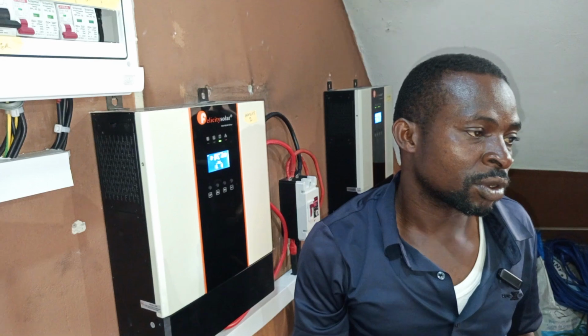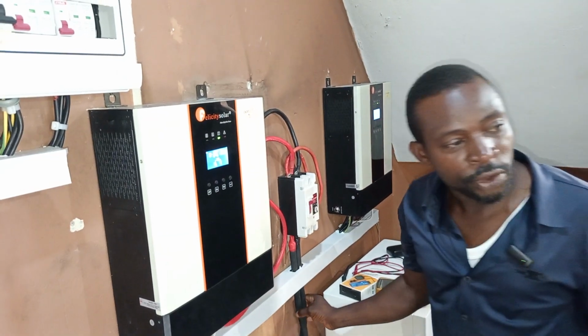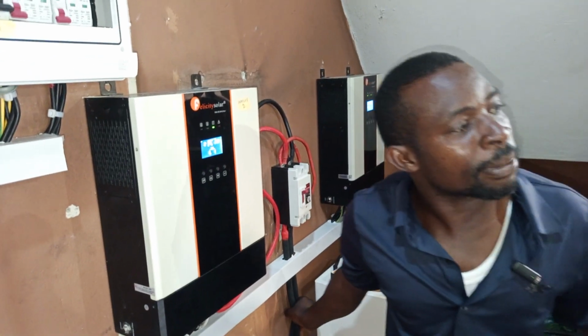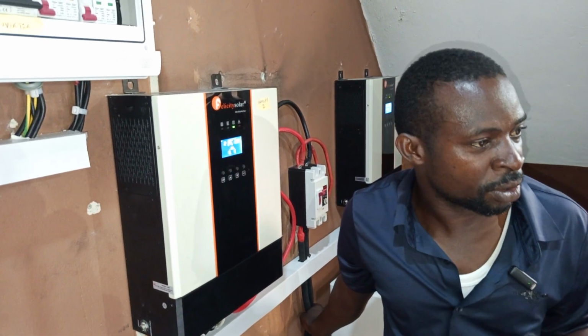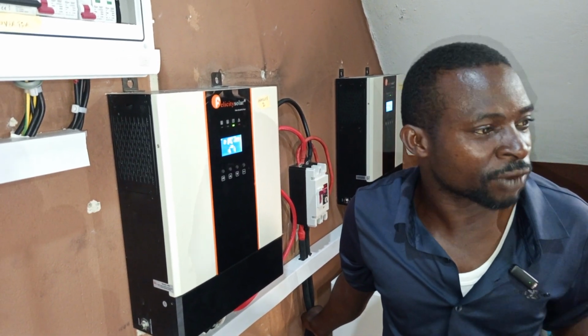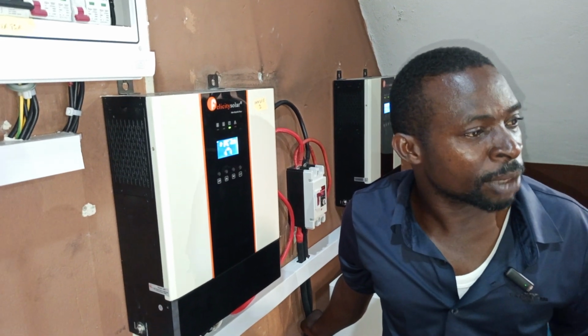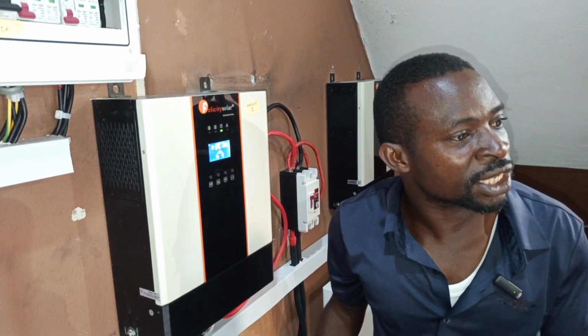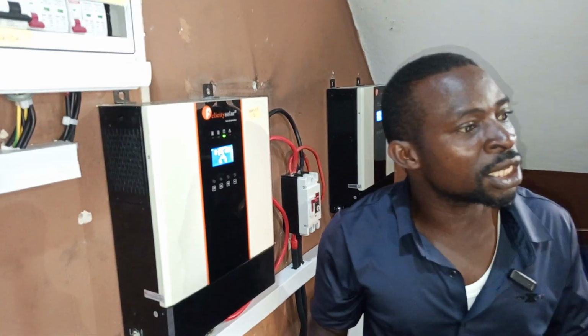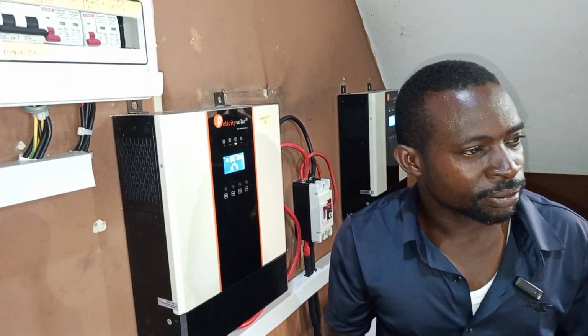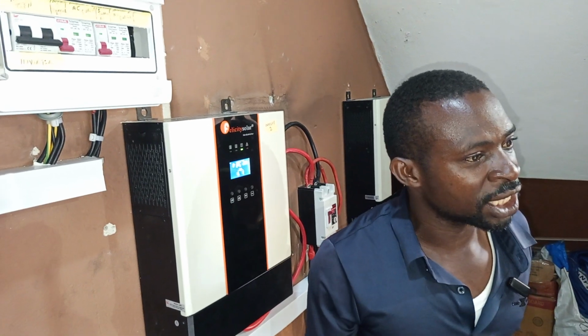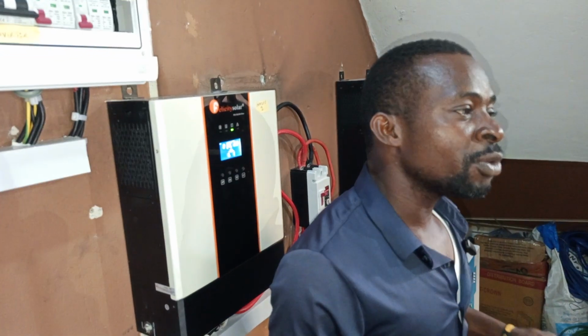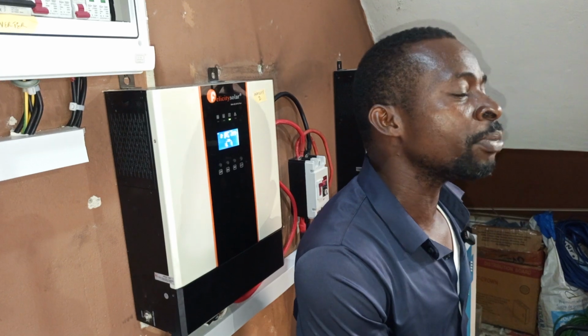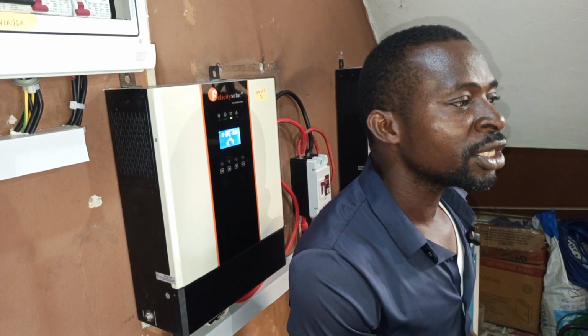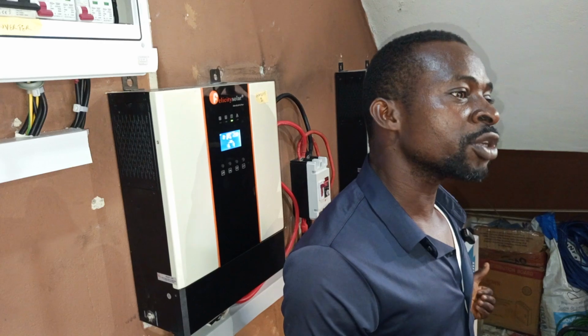There are cases we've heard of inverters catching fire. What are the causes? Some lithium batteries come with a smaller cable size, and we've written to so many manufacturers about this. Please change your cable size, especially when paralleling batteries. As you parallel lithium batteries, during charging they charge faster and the battery gets hot. If your battery cable gets hot and it's substandard, it will burst into fire.